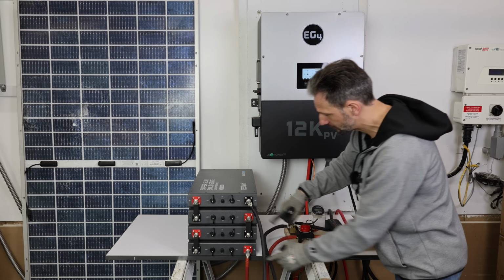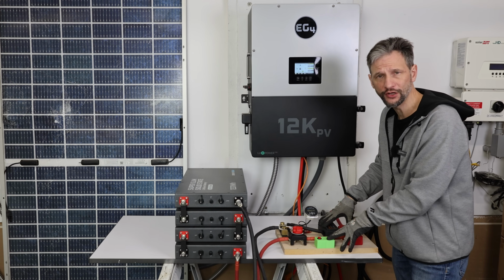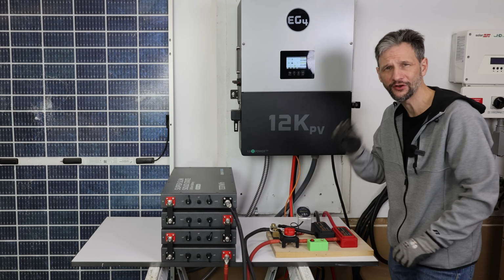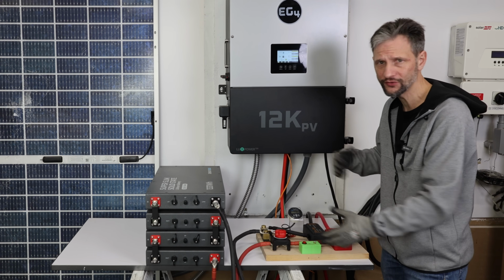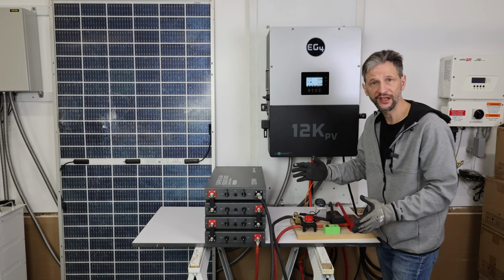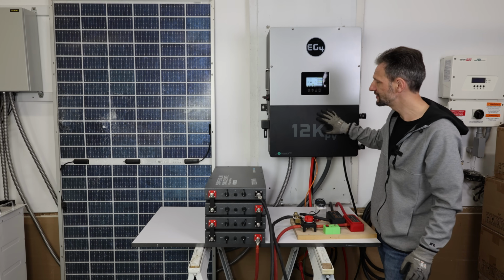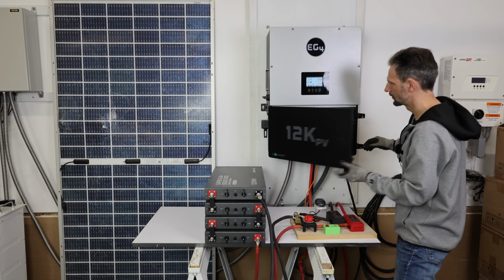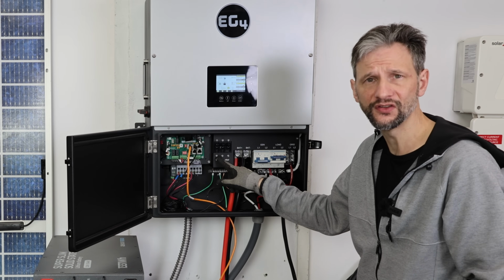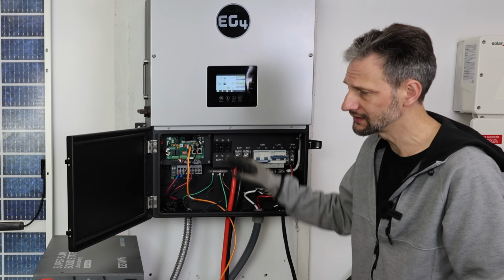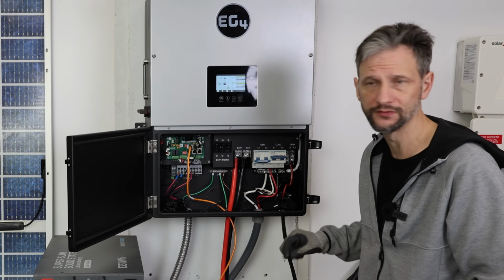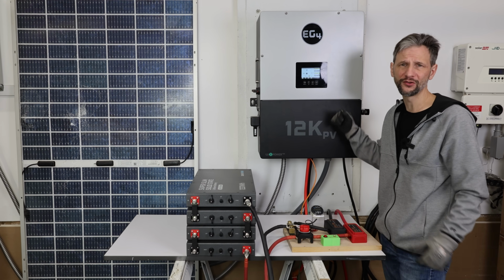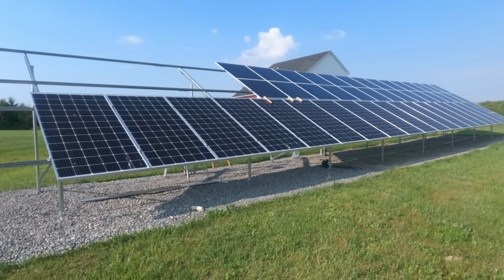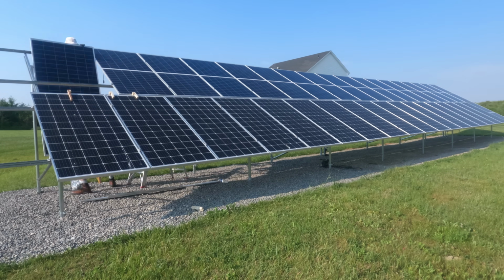Now I'm coming off of these posts into my Victron monitoring setup so that I can get some very accurate details on the amount of current being pulled through the system. But I could just connect this directly to my EG4 12K PV because it has its own breaker that I can easily disconnect these batteries with if I need to. I bought this inverter from Signature Solar almost a year ago to expand my solar system, and I've had no issues since I installed it.